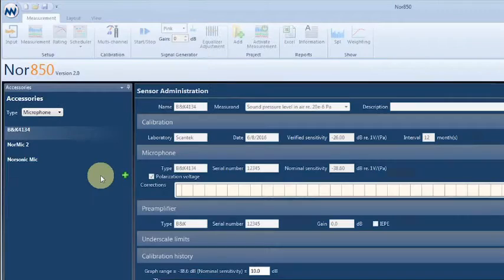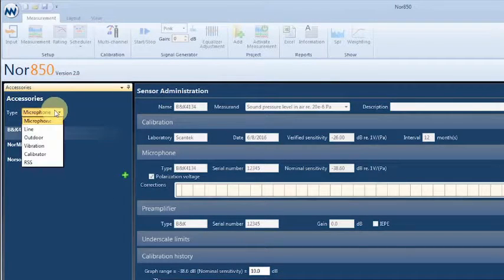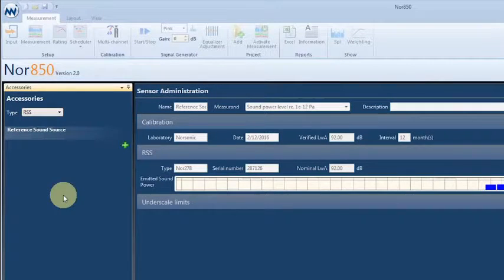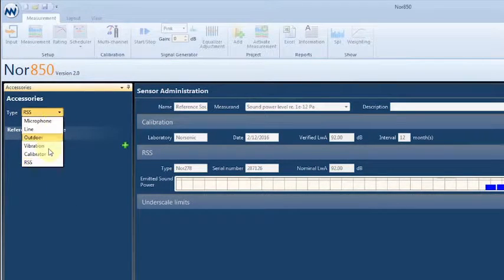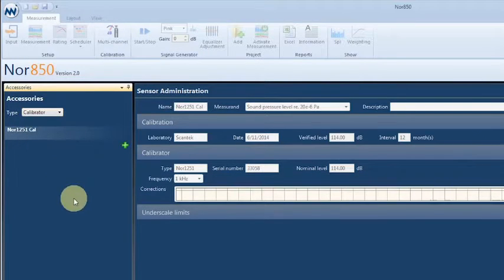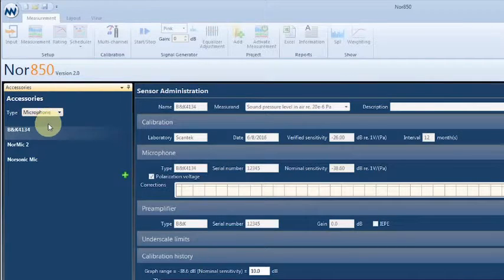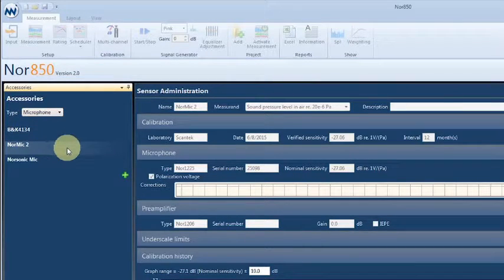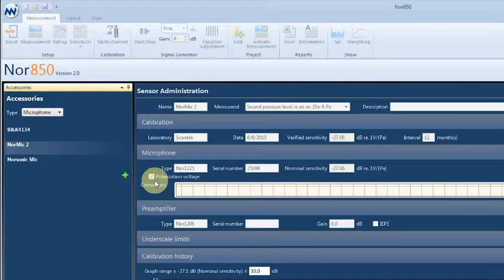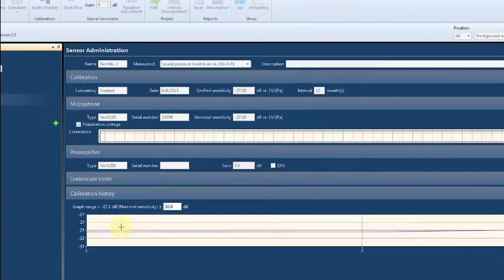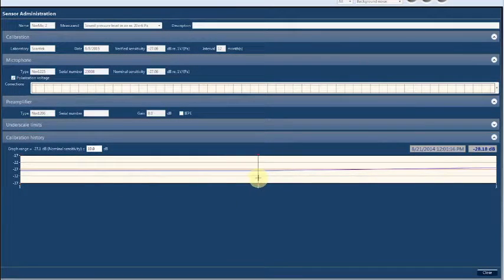The NOR850 software offers a small database for the management of all sensors used for measurements, including calibration and verification data. Data such as the model, laboratory calibration date, sensitivity, or polarization voltage can be defined for microphone sensors. Calibration verification history, or field calibration, is documented for each microphone and pre-amplifier combination.